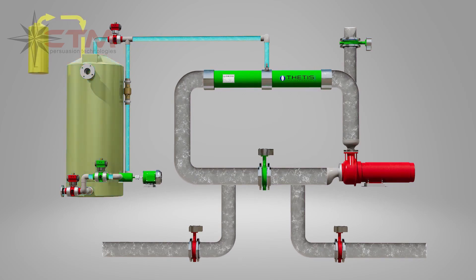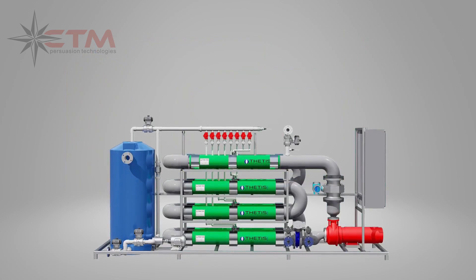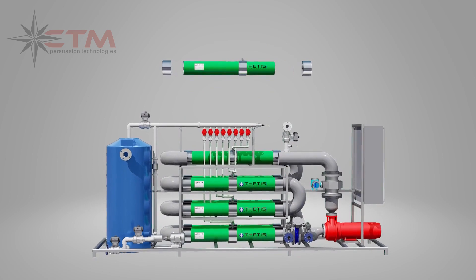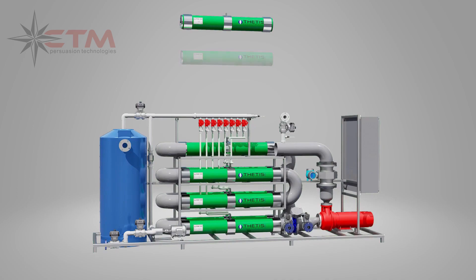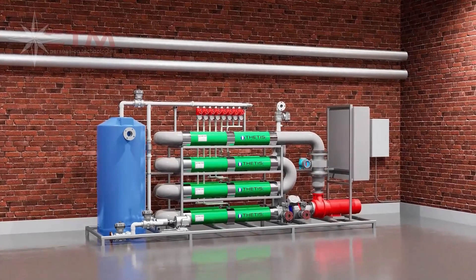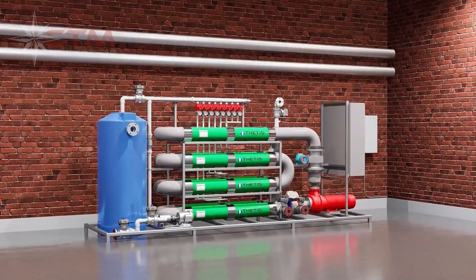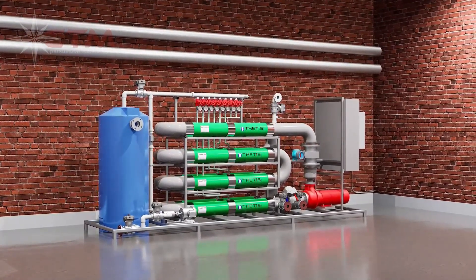Cleaning chemicals are added to the permeate tank. The mixed solution is backpulsed into the membranes, similarly to a backwash step alternating with soaking intervals to dissolve and remove fouling contaminants. If needed, one or more modules can be replaced in a skid. Fully assembled and factory tested filtration skids are installed at the customer's site. The commissioning process is typically between two and six hours.